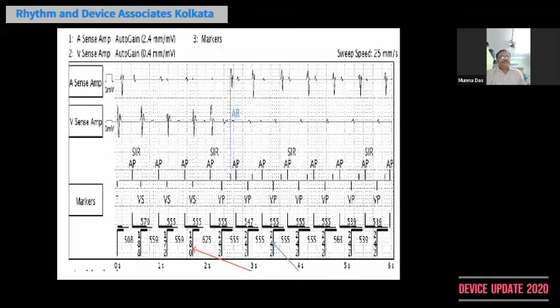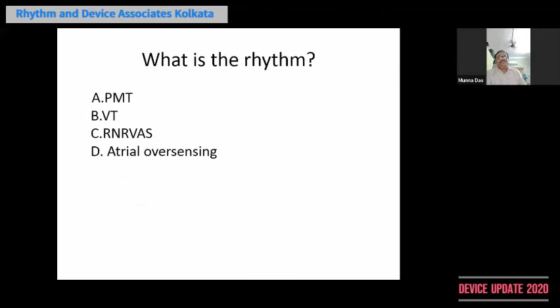So here it is non-reentrant. It is not like PMT, where the impulse is delivered by the pacemaker to the ventricle in response to the atrial sense event occurring outside the PVARP, and that completes the circuit through the retrograde VA conduction. Here it is basically repetitive non-reentrant VA synchrony. The pattern we should remember. Next slide. A potential complication of RNR VAS is an A pace in the atrial refractory period, which can produce atrial fibrillation. You can see it in the topmost strip.